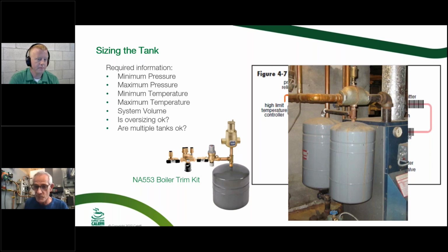The do's and don'ts in this picture right here, classic example of that tank on the left side of the picture doesn't have very good support other than the threads on that nipple, and that looks like a number 60, so that's going to weigh 90 pounds when it's waterlogged. So I doubt that pipe nipple is going to be up to that task. So yeah, this is a perfect example of when that sheet metal screw might come into play. If that thing's all waterlogged, then you don't really feel like taking a bath that day.